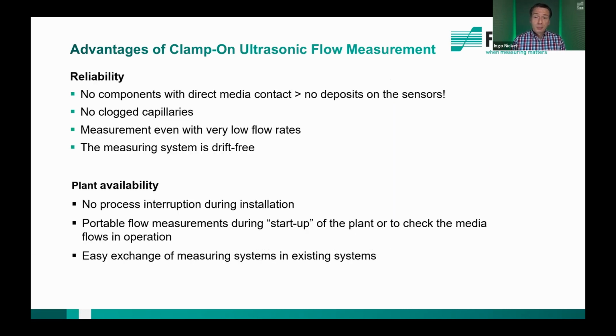I think reliability and high plant availability are very important aspects for plant and unit operators. And why is ultrasonic flow measurement a highly reliable measuring solution for chemical plants? There are no wetted parts which can be affected by the media or the fluid. This means corrosion or any kind of deposit formation on the sensor cannot affect the measurement, and there's no risk of clogging in the pipe. Furthermore, the design allows metering at very low flow rates and provides a completely drift-free measurement, which is also unique compared to other flow measurement technologies.